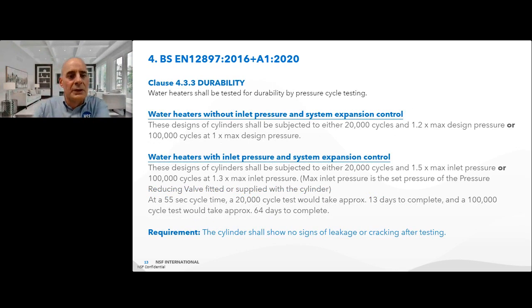Clause 4.3.3 then is durability. So the water heaters should be tested for durability by pressure cycle testing. Water heaters without inlet pressure and system expansion control. So these designs of cylinders should be subjected to either 20,000 cycles at 1.2 times the maximum design pressure or 100,000 cycles at the maximum design pressure. But for systems in the UK, these are covered by the next group.